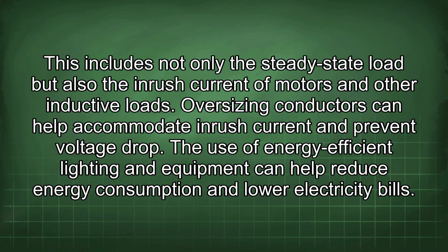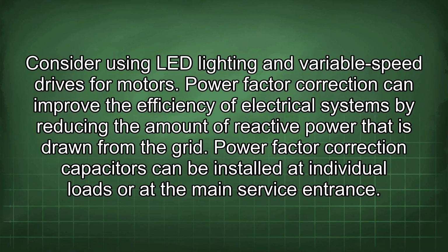The use of energy-efficient lighting and equipment can help reduce energy consumption and lower electricity bills. Consider using LED lighting and variable speed drives for motors. Power factor correction can improve the efficiency of electrical systems by reducing the amount of reactive power that is drawn from the grid. Power factor correction capacitors can be installed at individual loads or at the main service entrance.